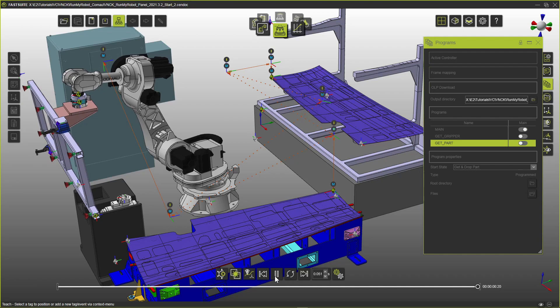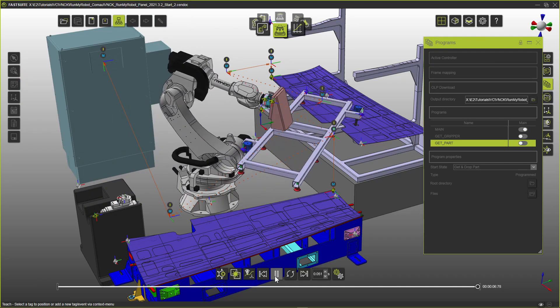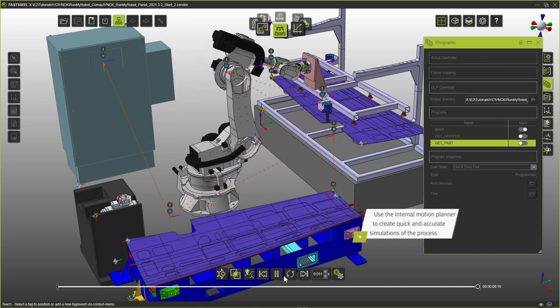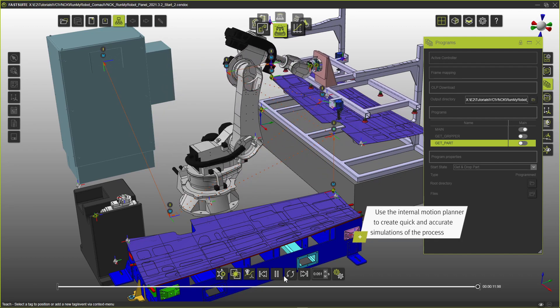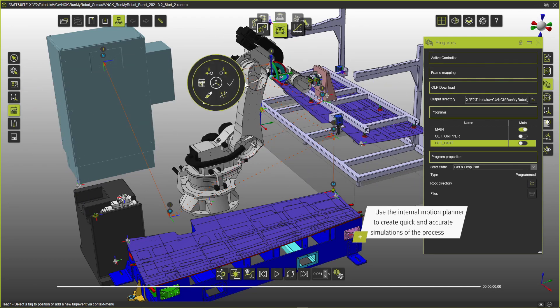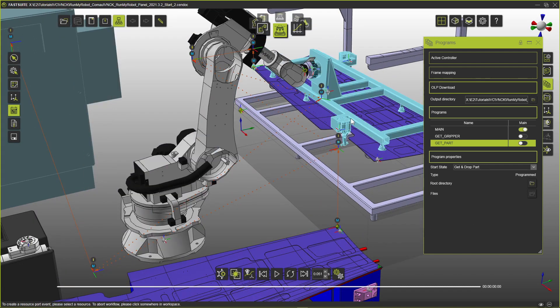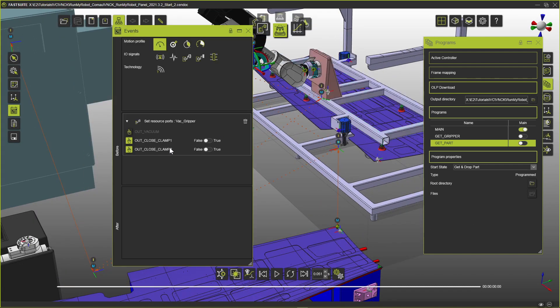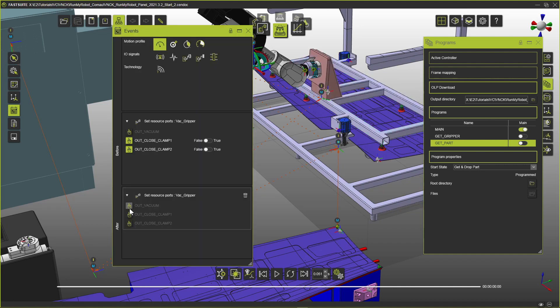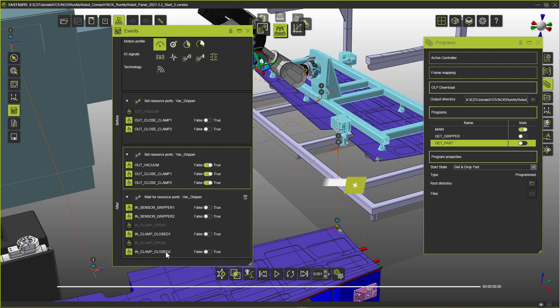Next in line is the get part sub-program. We taught the positions already. Now we add all the required port events to pick up the part from the rack and drop it off at the tooling location. Note that we don't have to worry about the signal names or numbers on the S840D controller side. FastSuite-E2 handles this automatically in the background.